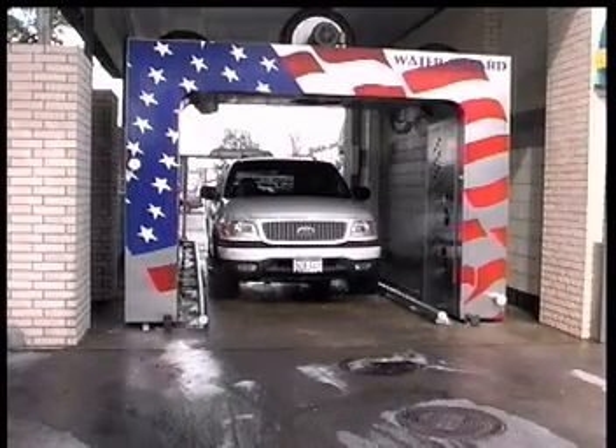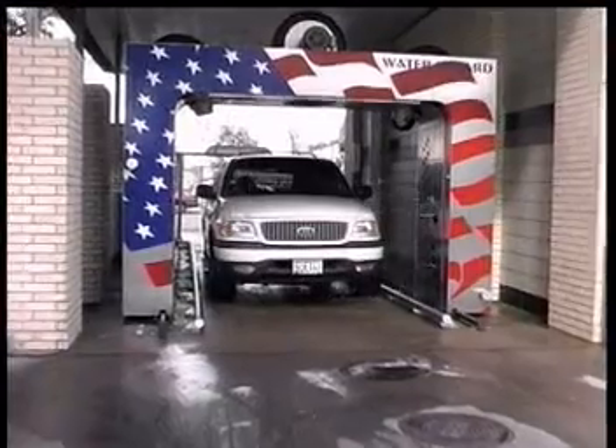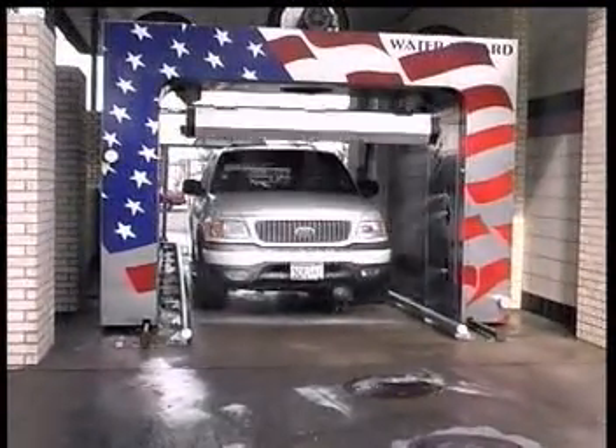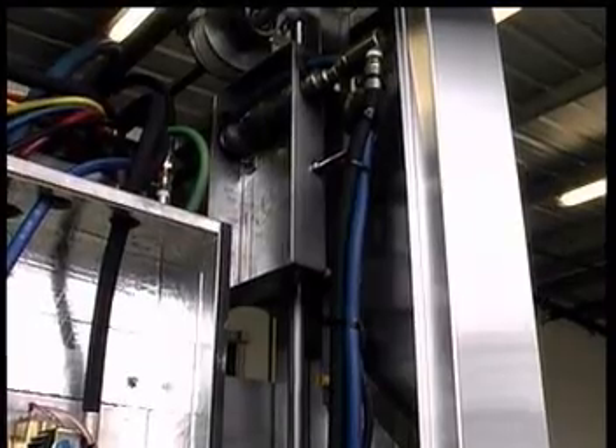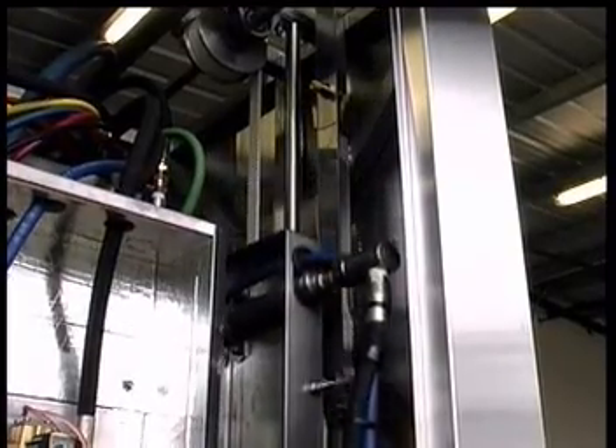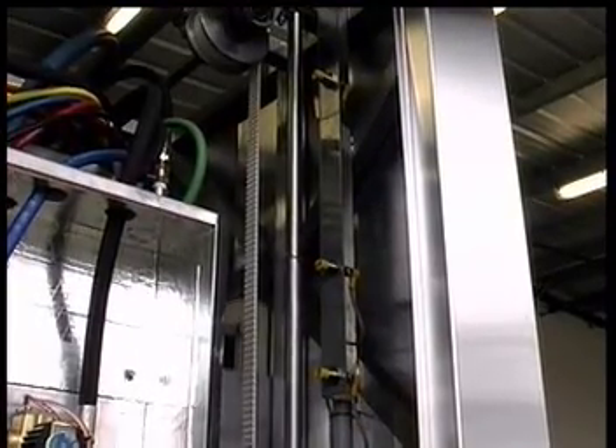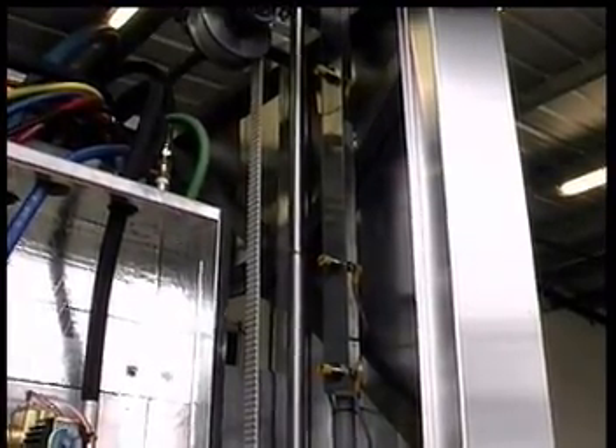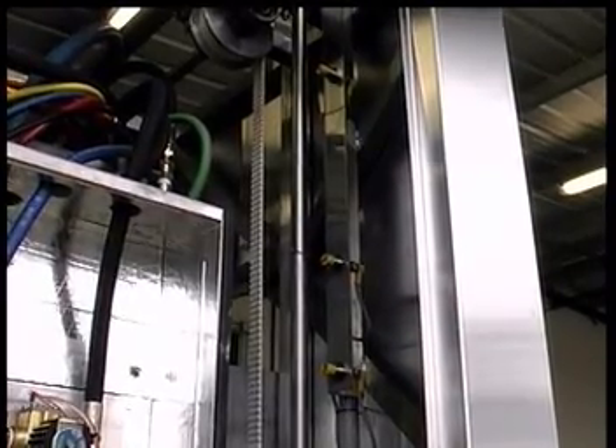The Water Wizard performs a diagnostic check on all proximity switches at the beginning of each wash cycle. If any of these proxes do not report the proper on or off signal for startup, the processor will report a fault. Check the top prox for proper operation.